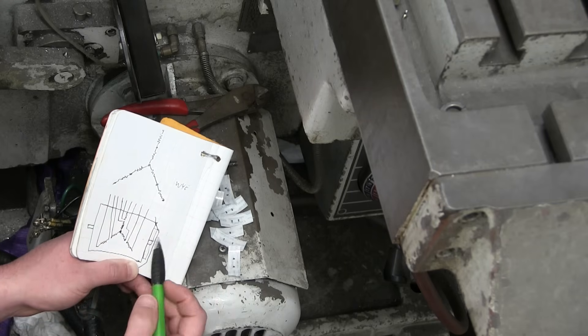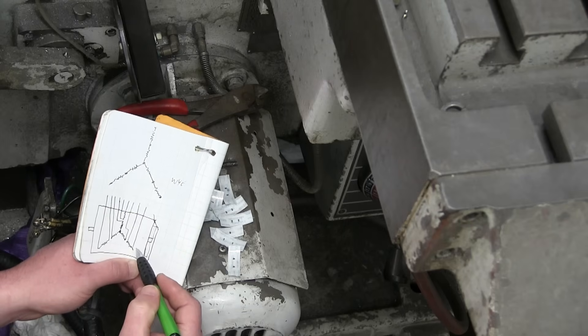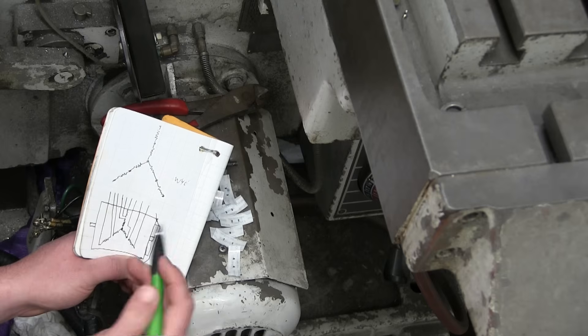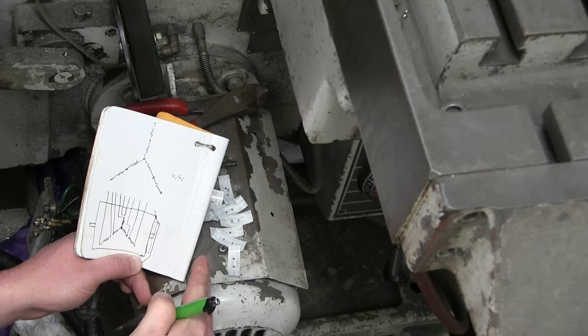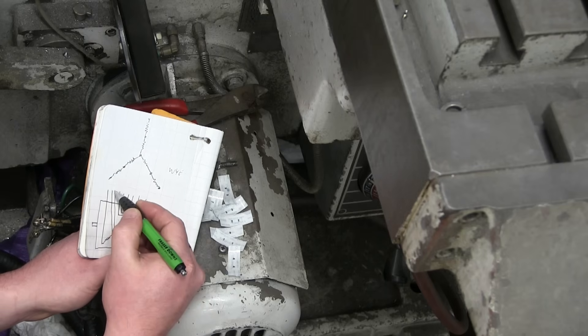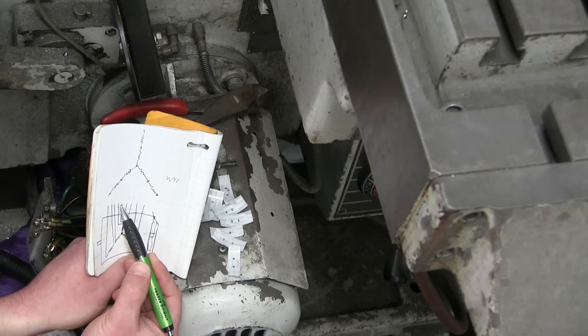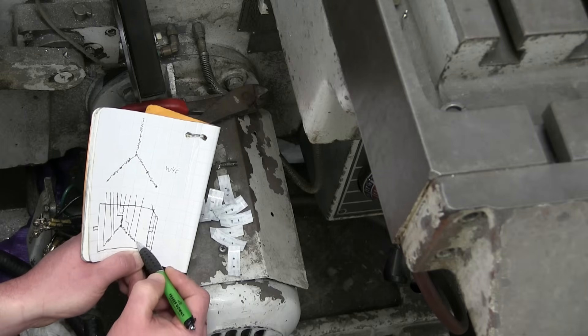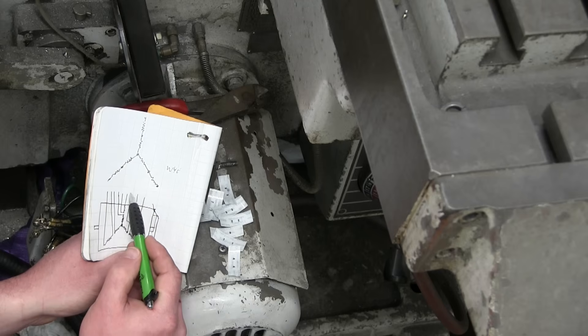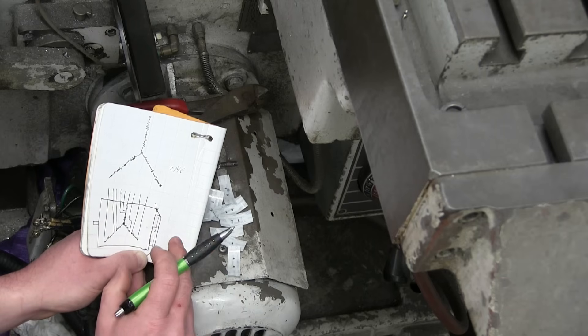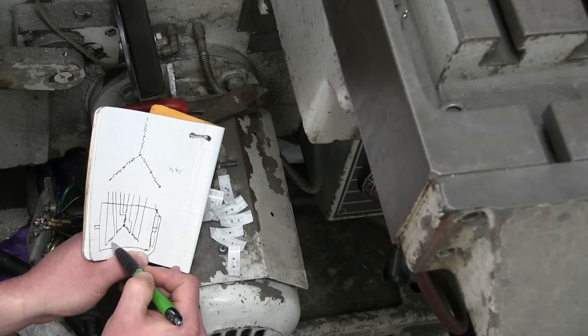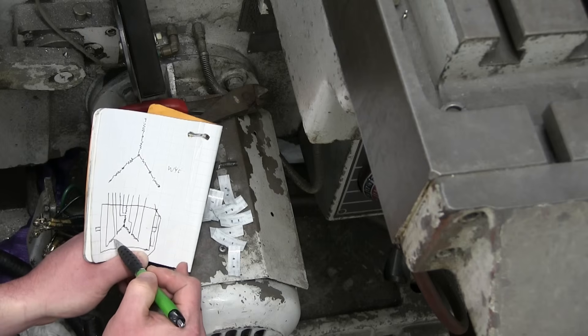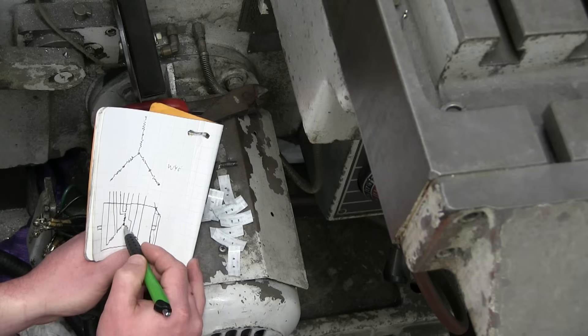Now if we want the high voltage, we need more resistance, otherwise it burns out, more impedance. So what we do is we connect up these guys. This guy will get connected here, and then this guy will get connected here, and then this guy. All the center taps get connected, and then on the outside that's where we put the three phase in. So we'll put 440 here, we'll put 440 here, we'll put 440 here.